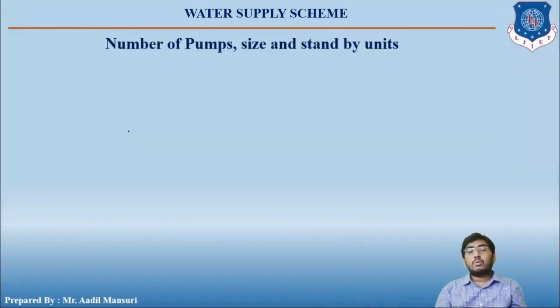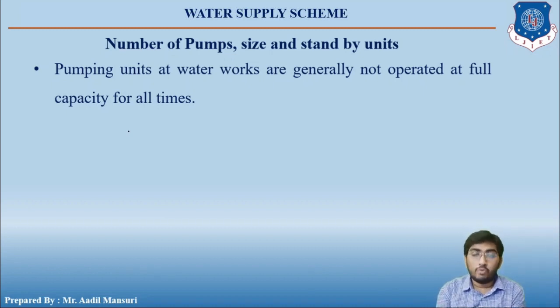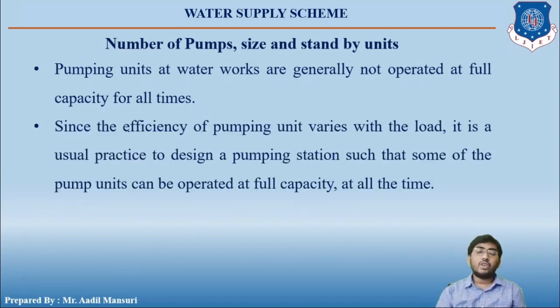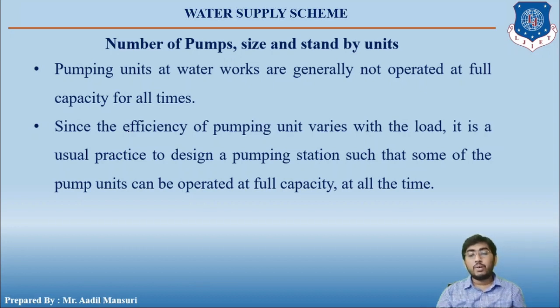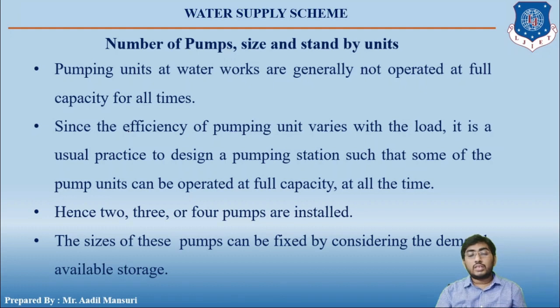Pumping units at waterworks are generally not operated at full capacity at all times. Since the efficiency of a pump unit varies with load, it is usual practice to design a pumping station such that some pump units can be operated at full capacity at all times. Hence, two, three, or four pumps are installed.